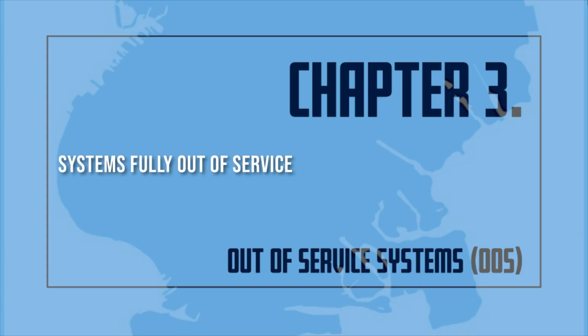Systems fully out of service. The impairment coordinator/building owner shall ensure that the local administrative fire company, a master fire suppression piping contractor, Class A or B, or a master licensed plumber, as restricted, has placed one white disc 8 to 9 inches in diameter on all affected fire department connections. A red tag shall be placed at the main control valve indicating the standpipe company name, date of removal from service, and anticipated return to service date.